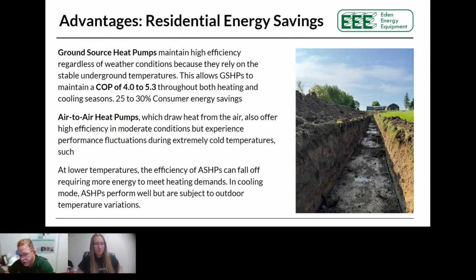The other application you'll see is, rather than dumping it out into the ground loop, they'll have a thermal storage medium that they'll charge. So if your outdoor ground loop is at 50 degrees, arbitrary but realistic numbers, and you want to increase your COP by increasing the ground loop temperature, other designs will tie the solar thermal to a buffer in the middle — the indoor unit — and lift the 50 degrees to, let's say, 70 degrees before it goes through the unit.